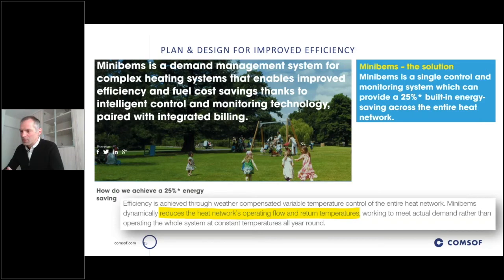Why is this important? Because when we design a district heating network, we have to assume a certain delta T, so we have a supply temperature, but it's also very important to have good certainty about the return temperatures. By using the Minibems control system on top of the network, we can assume during the design stage a solid return temperature, so we will assume a delta T of 30 degrees, which can be maintained.